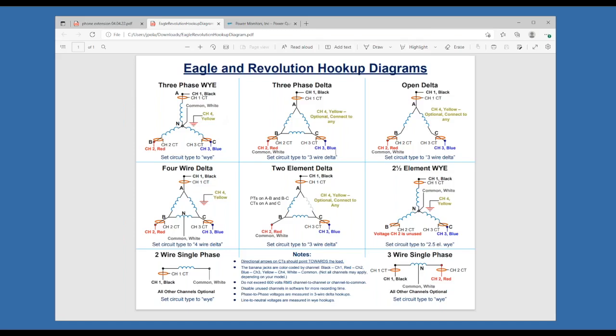The other option is a 3-wire delta, so if you want phase-to-phase voltages, or if you're working on a true delta configuration where there is no neutral, we still need to power the recorder up so the white and the red go on the same phase. And that 3-wire delta works for open delta and also 2-element delta. There is a 2.5 element Y that you can select, and also a 4-wire delta configuration.